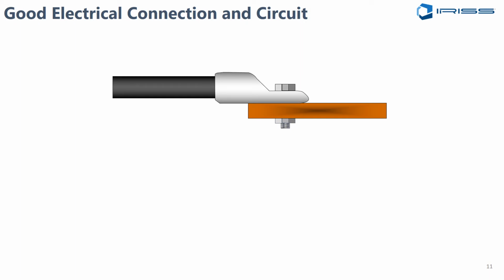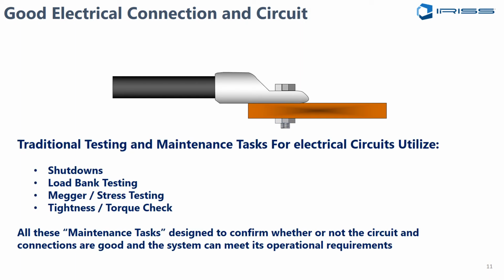So what I have here is a good electrical connection. Traditional testing for this type of task, we have to shut down. We can maybe do load bank testing, megger testing, tightness and torque checks, etc. There's a whole bunch of testing I can do on this circuit to show that it's correct. Now all these maintenance tasks are designed to confirm whether or not the circuit connections are good and the systems meet their operational requirements.